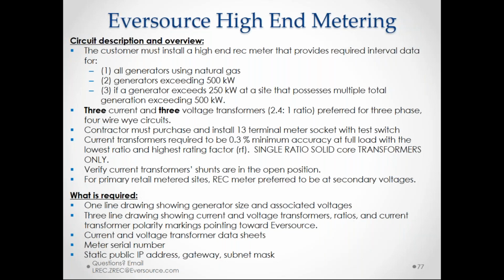I know this isn't on the slide, but I've certainly seen cases where customers or contractors have designed a 480/277 volt system where the inverters are at the higher 277 voltage, but the service voltage is at 120/208, so they have a customer-owned transformer to take down the voltage. We would always, in those cases, recommend that the REC meter be placed on the high side of that customer-owned transformer, as close to the inverters as possible. That's just good design practice because it's going to minimize the potential losses.